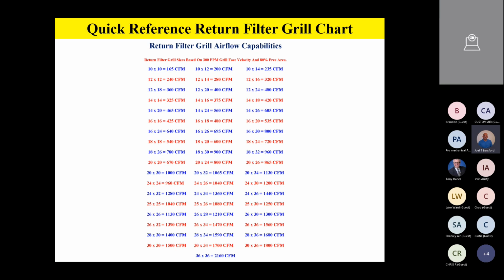So that 300 is a hard, solid Manual D number that kind of trumps even a filter grill manufacturer, because what I'm trying to say is Manual D says do not exceed 300 feet a minute velocity across that filter. And so that criteria of 300 feet per minute has to do with the filter, not so much the grill. So please keep that in mind, and that's the maximum recommended filter face velocity according to Manual D. So by all means, if you've got a different grill than 80% free area, plug that into the formula. But this little chart that I gave you, if you figure 80% free area and 300 feet a minute velocity, is conservative. You will never get in trouble with this filter grill.